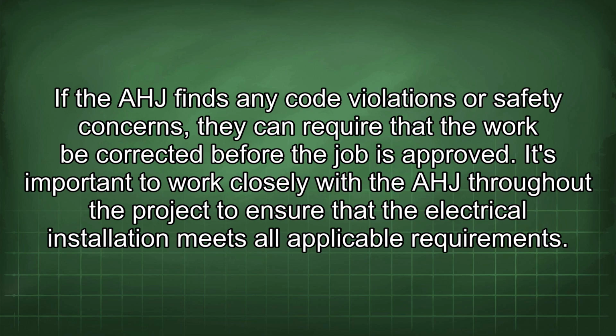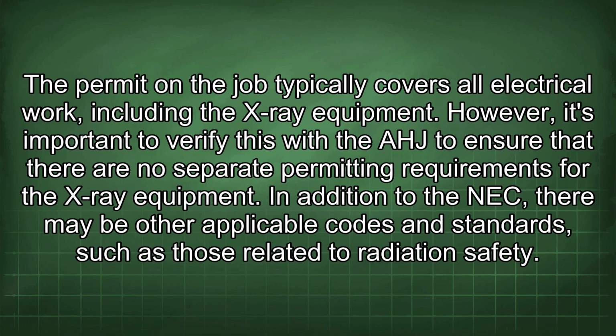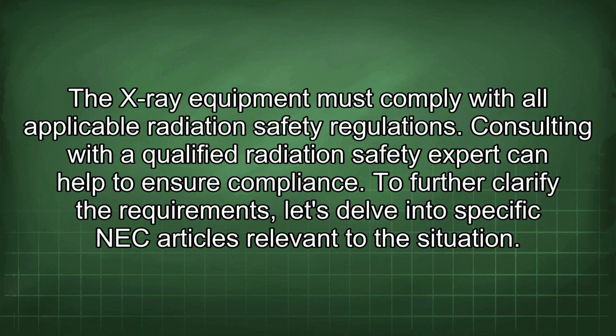The permit for the job typically covers all electrical work, including the X-ray equipment. However, it's important to verify this with the AHJ to ensure that there are no separate permitting requirements for the X-ray equipment. In addition to the NEC, there may be other applicable codes and standards, such as those related to radiation safety. The X-ray equipment must comply with all applicable radiation safety regulations. Consulting with a qualified radiation safety expert can help to ensure compliance.